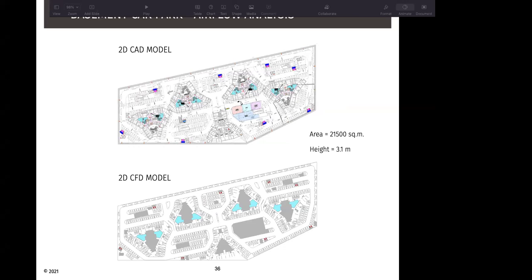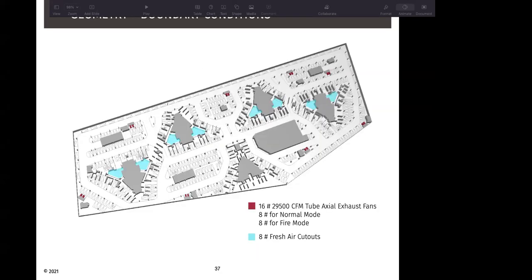And then there are some blocked lobbies, staircases, lift lobbies, tank area, pump area, all of that has been blocked off. We assume that these parts of the car park have been blocked off by fire doors. This is the 3D CFD model for the car park. So there are 16 tube axial fans, 8 in normal mode and 8 in fire mode, which are marked in red, and the 8 fresh air cutouts have been shown in blue.